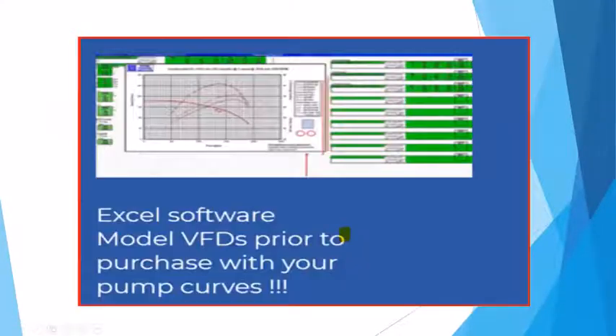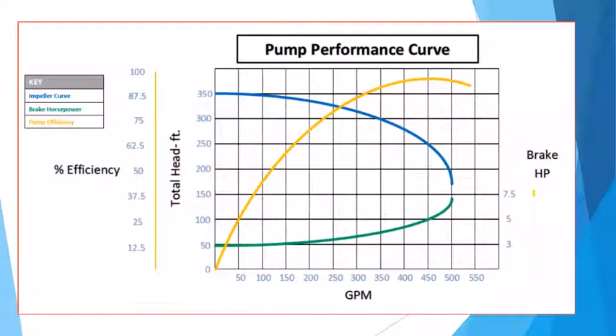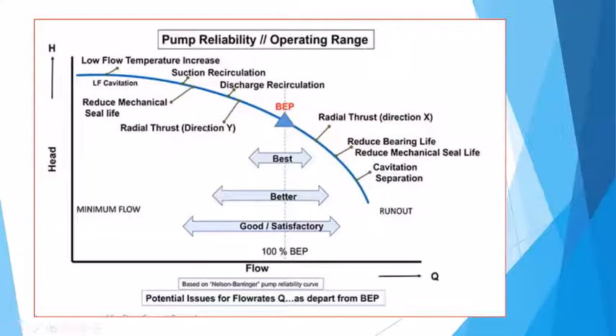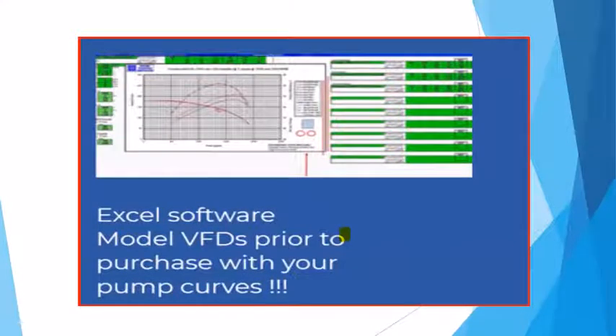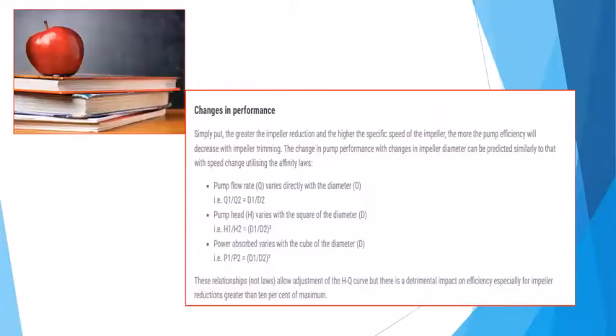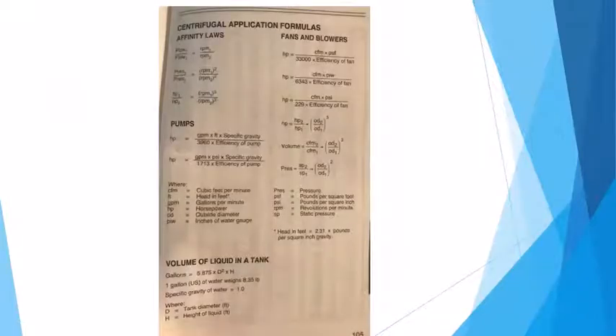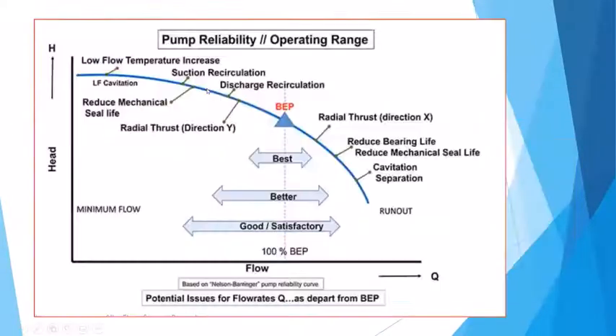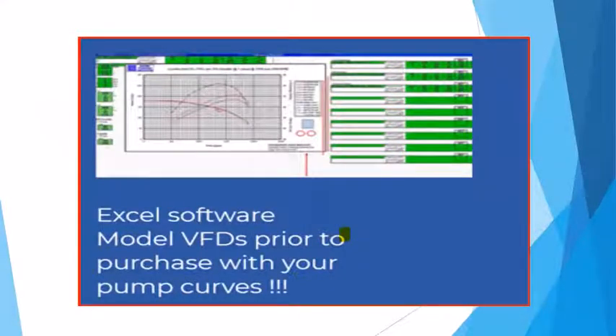And sometimes it's not known, and then you go add a new filter in the system, or you put in a new set of sprinkler heads, changing the head pressure. You've got a filter in there that may be dropping 10 or 15 pounds across the pump. Again, that affects the total efficiency of the system. So that's one thing that's also important, and Rob also has a lot of information about that. It's not just the cube law, the affinity law of savings. It's the efficiency of every item.